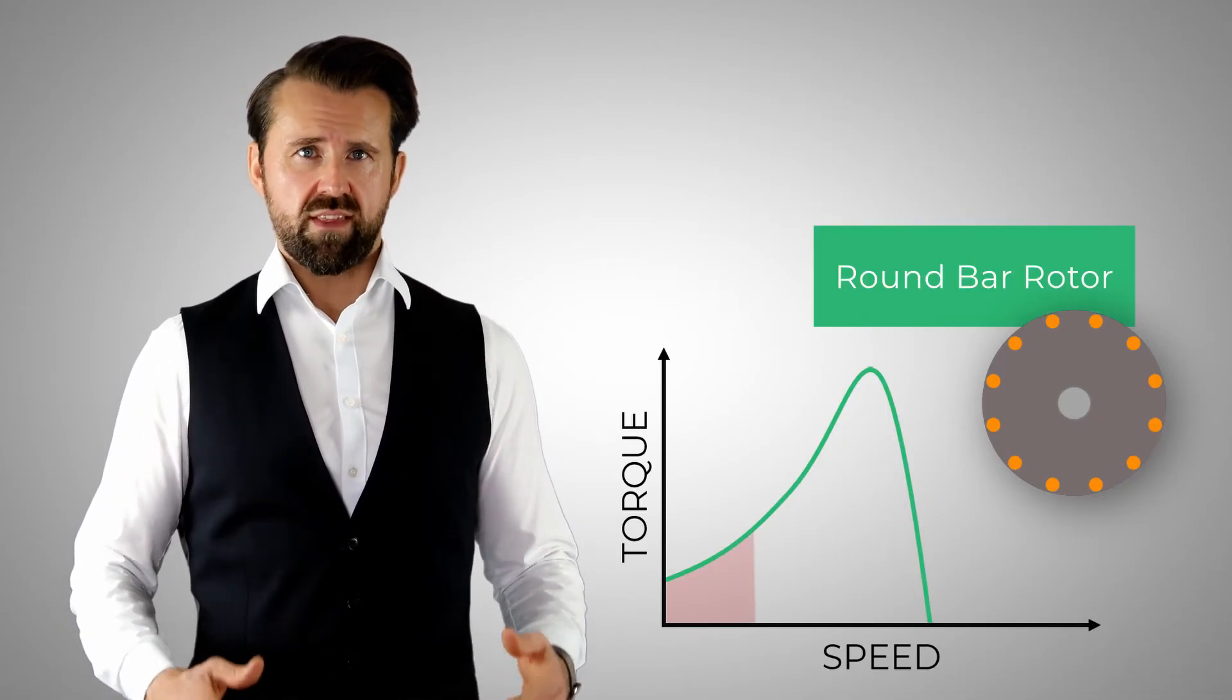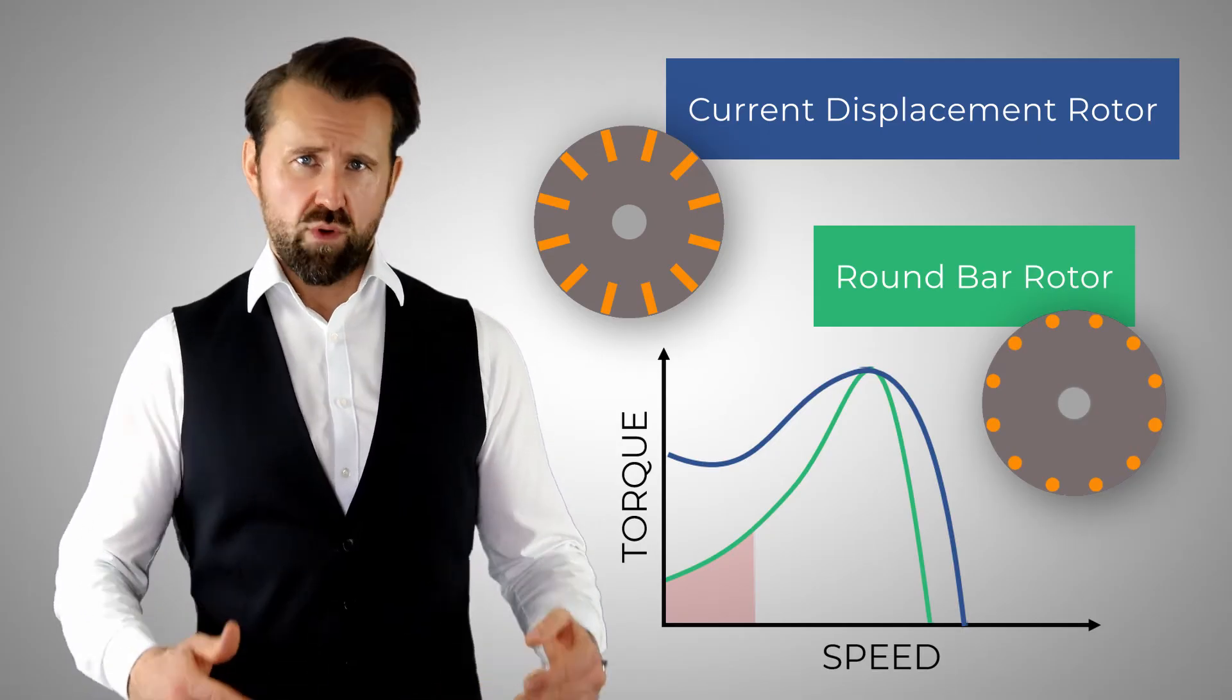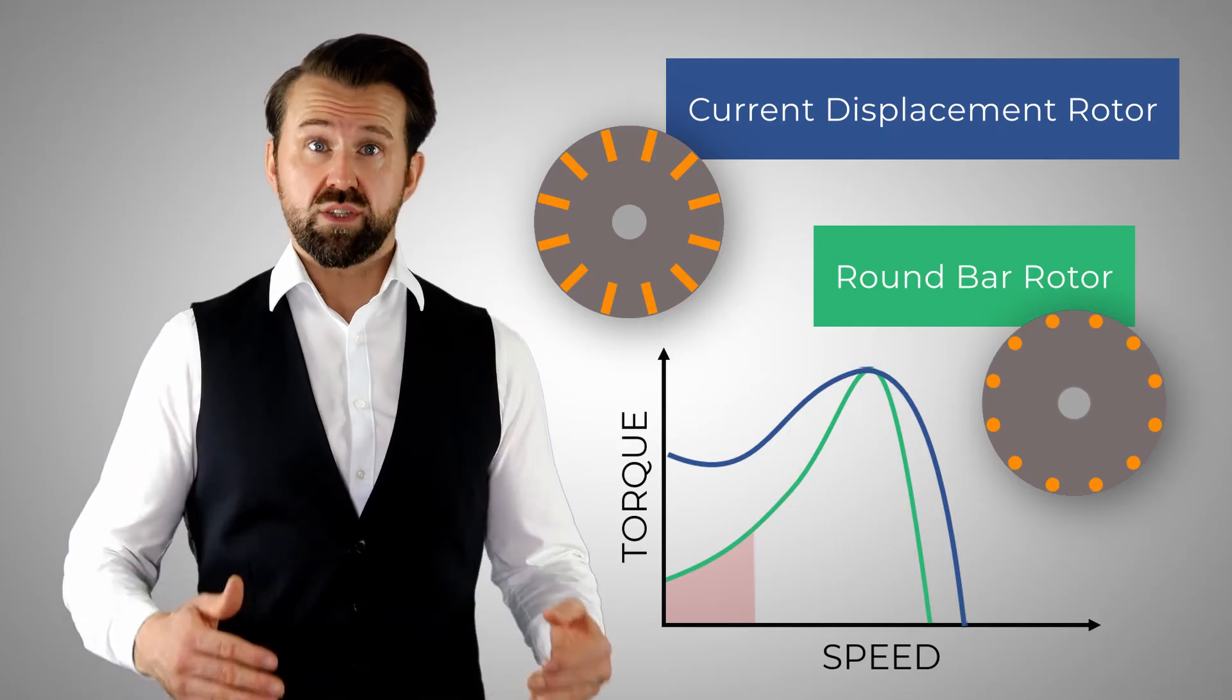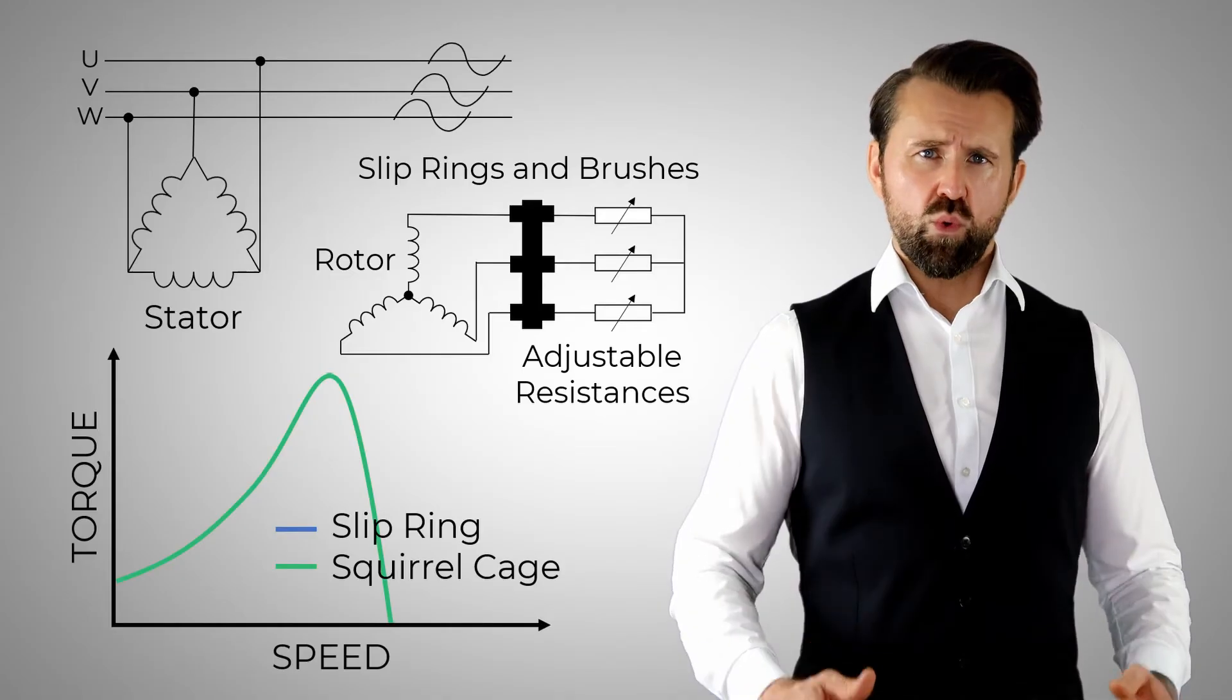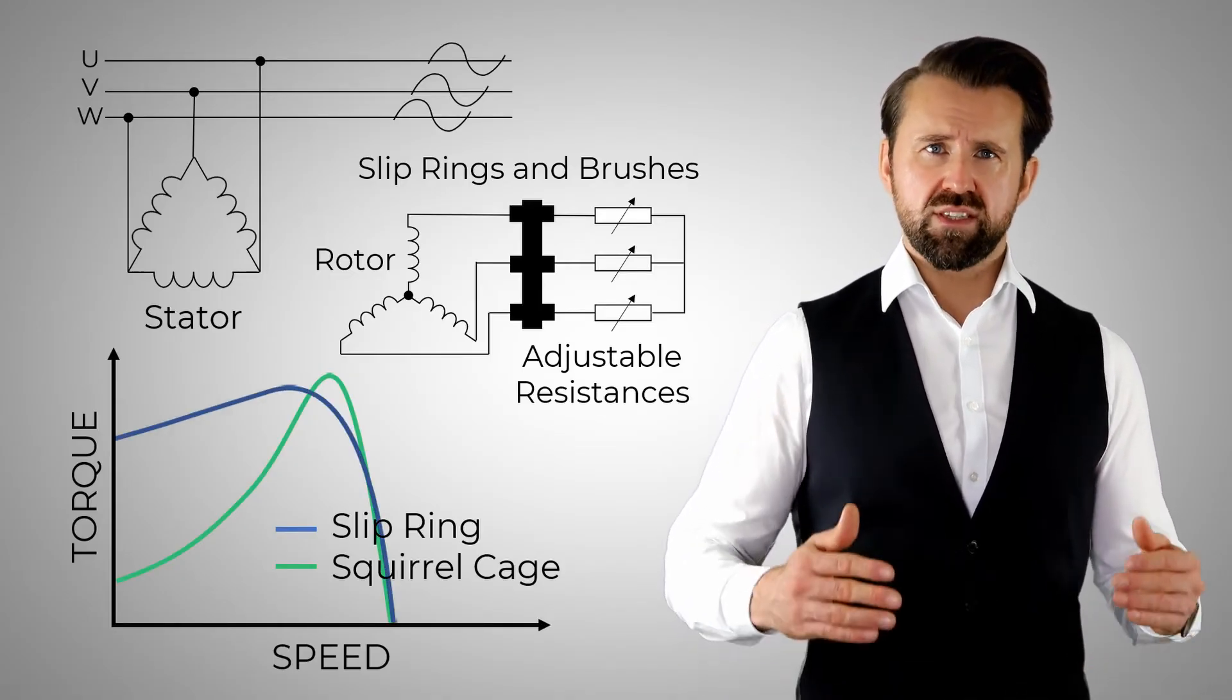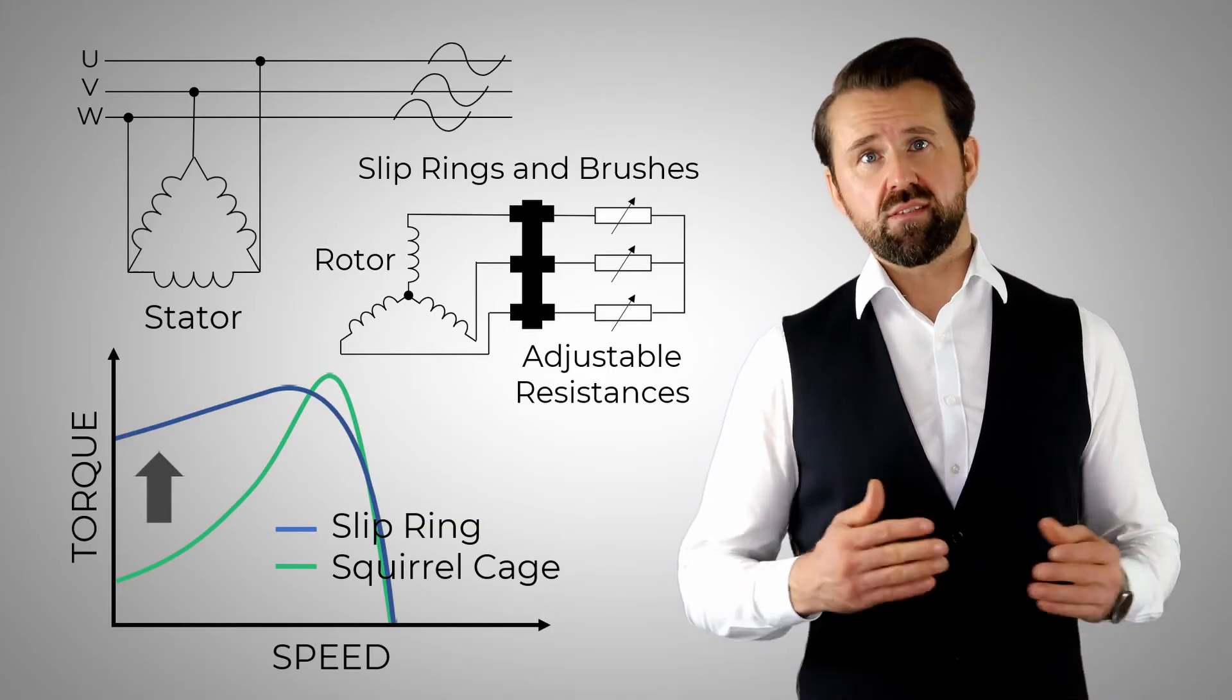To increase the torque in the lower speed range, a current displacement rotor can be used. For example, rectangular bars are used instead of round bars. This increases the resistance of the rotor in the lower speed range and therefore also the torque. Another way to increase the torque in the lower speed range is to use a slip ring rotor. With a slip ring rotor, the resistance is changed by externally variable resistors. In the lower speed range, the resistance is increased externally, thereby increasing the torque.